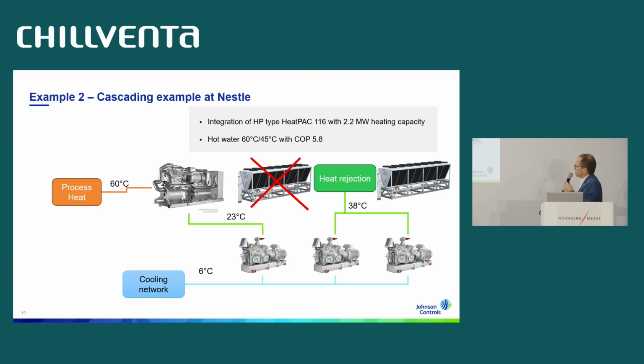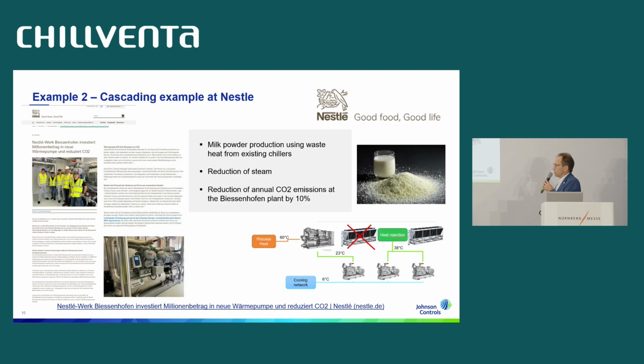This is a HeatPAC here on the cooling side, taking the rejected heat from the chiller section, then providing process heat at 60 degrees Celsius with a COP of 5.8, because we were using rejected heat from the coolers. So that's amazing. And we were serving 2.2 megawatt heating capacity with a very simple design HeatPAC system. And towards our customer, this was really saving money and CO2 emissions.